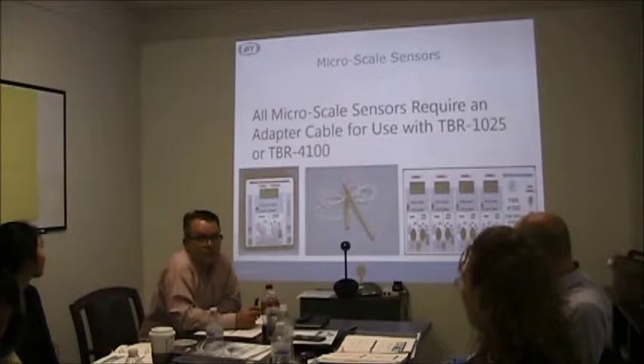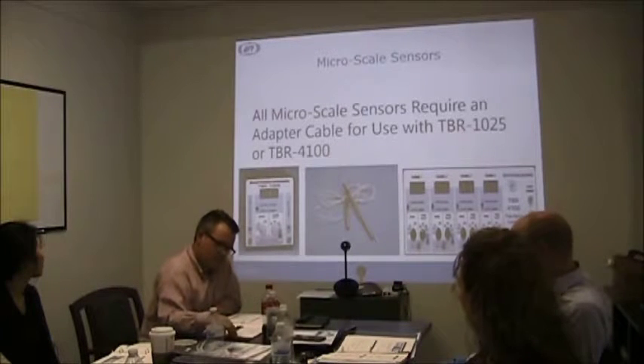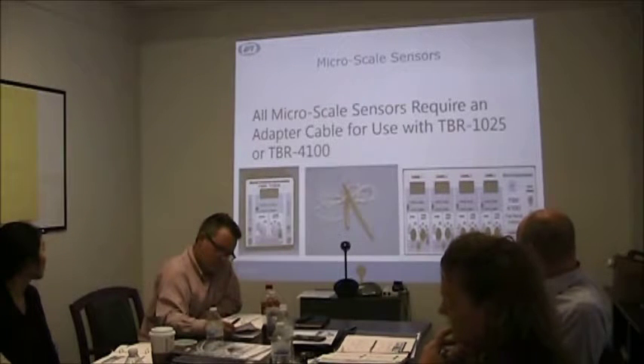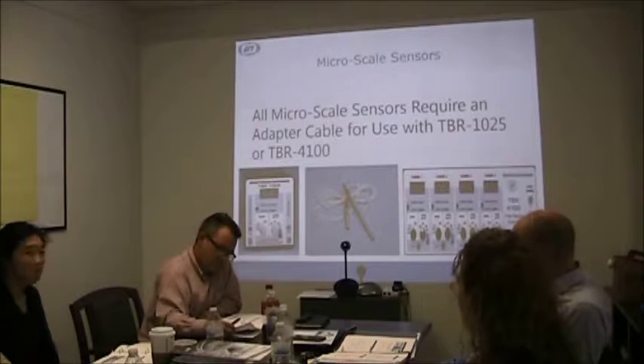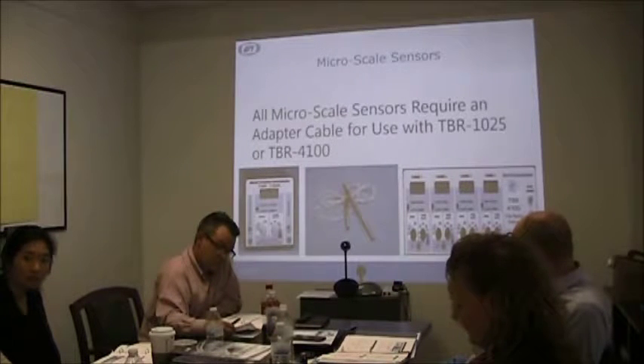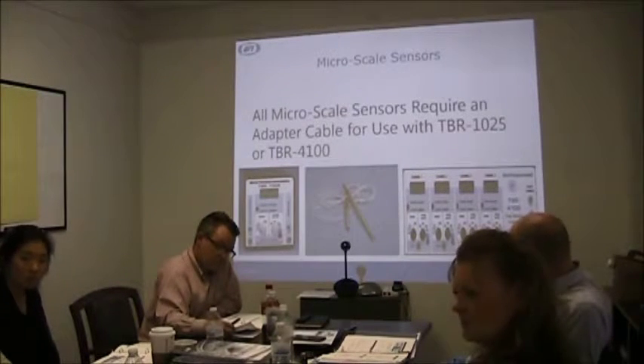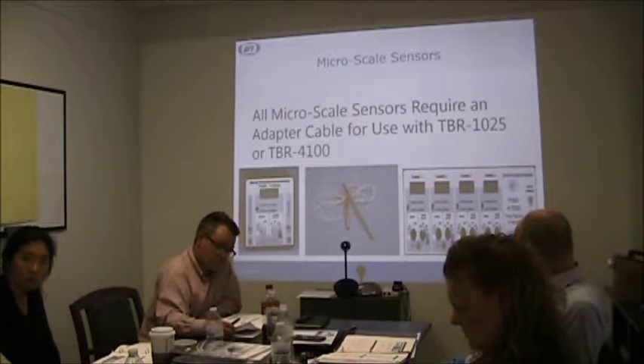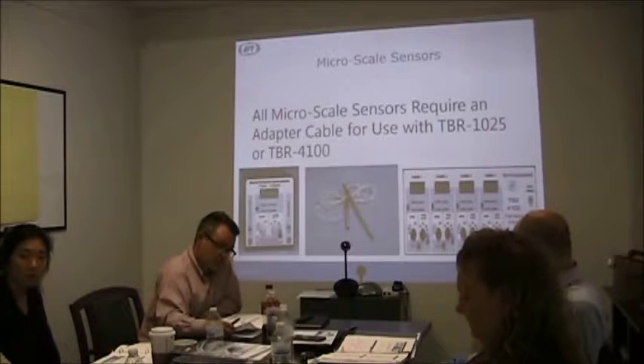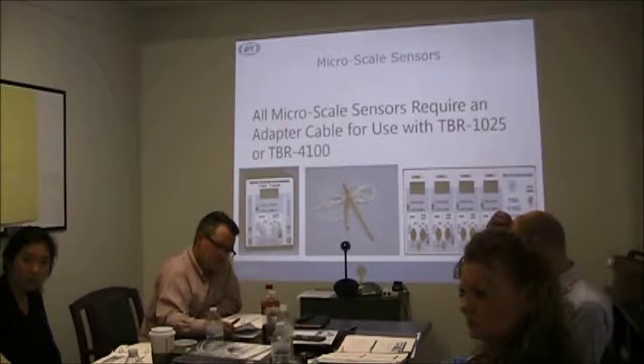All of the predetermined poise voltages for the sensors will dictate the way all of our specs are reported. So, as an example, for nitric oxide, the voltage that's applied is about 860 millivolts, plus or minus a couple. If it differs wildly from that value, all the numbers and specs are going to be vastly different. So that's something very important with the design of the system: if it is radically different from what it's supposed to be set at, it's going to create a lot of variance in the data reported.